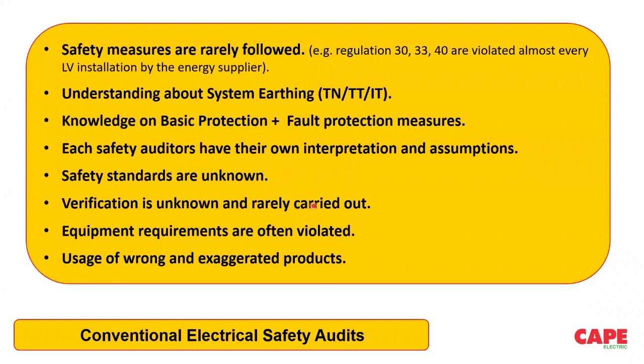Safety standards are unknown, verification is unknown and rarely carried out. As I said, please note that I am not using the word safety audit, I am using the word verification. Verification audits are made, but the result of the audit is a question. Verification is rarely carried out. Equipment requirements are often violated. Usage of wrong and exaggerated products. As I said, the exaggerated products are things like digital earthing and chemical earthing. Nowadays, most of these chemical earthing companies become electrical safety auditors. So when a chemical earthing company becomes an electrical safety auditor, the result is that he will try to recommend 25 more earth pits. The client buys it and installs it. This is actually not correct.